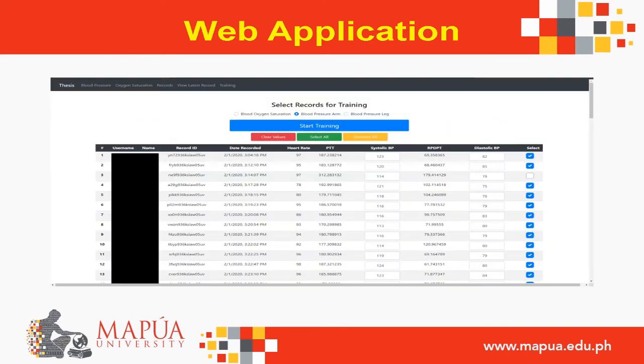Records can be seen in the web application and the training for the linear regression was incorporated. Each record consists of the heart rate, pulse transit time PTT, systolic blood pressure, R-peak diastolic peak time RPDPT, and diastolic blood pressure. The pulse transit time is used to obtain a regression model for the systolic blood pressure, while the RPDPT is used to obtain a regression model for the diastolic blood pressure. The actual systolic and diastolic blood pressures are obtained using a commercially available blood pressure monitor, and the recordings on commercial devices are entered here to proceed with the training. All data to be part of the training can be selected as well.